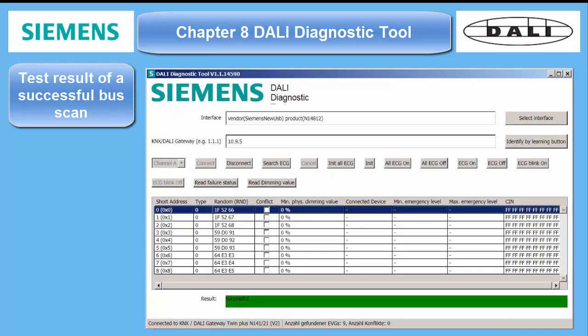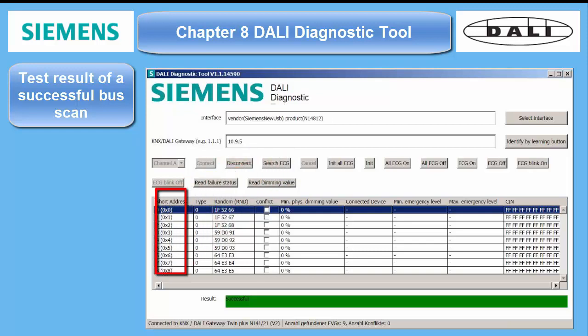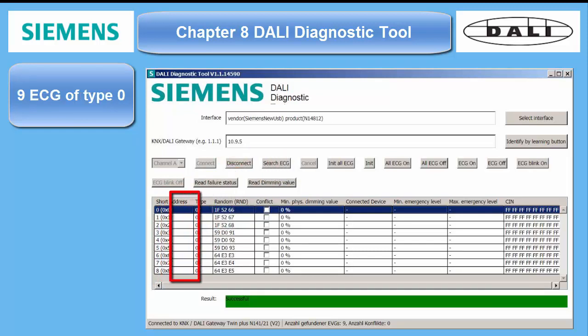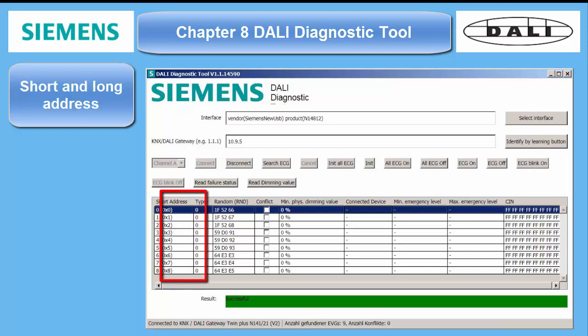On this screen we have the fault-free result of a bus analysis by pressing Search ECG. The tool has found nine ECGs, all of type 0 fluorescent tubes, but can also be other ECG types. In my case I have used three three-channel LED drivers, which use the generic type 0.